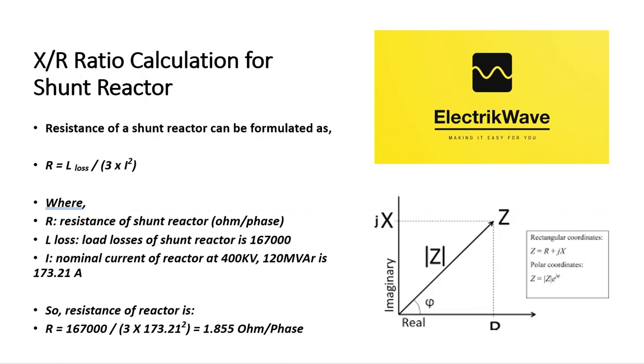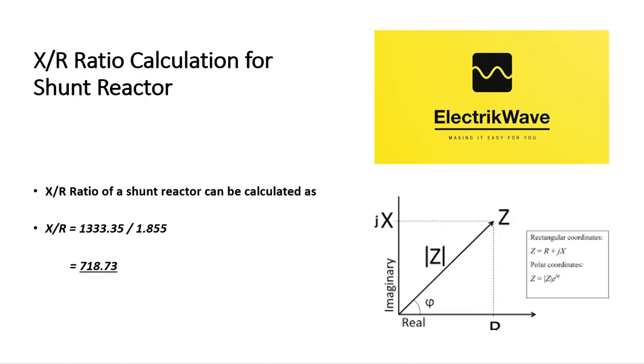Resistance of a shunt reactor can be formulated as R equals L_loss divided by 3 times I squared, where R is resistance in ohm per phase, L_loss is load losses of shunt reactor (167,000 W), and I is nominal current at 400 kV, 120 MVAR, which is 173.21 A. So resistance of reactor R equals 167,000 divided by (3 × 173.21²) equals 1.855 ohm per phase. Therefore, X/R ratio of the shunt reactor equals 1333.35 divided by 1.855 equals 718.73.